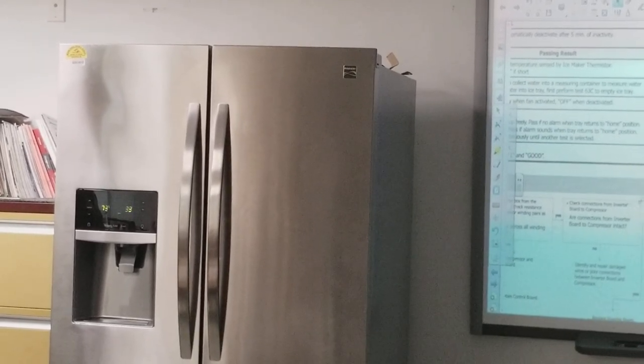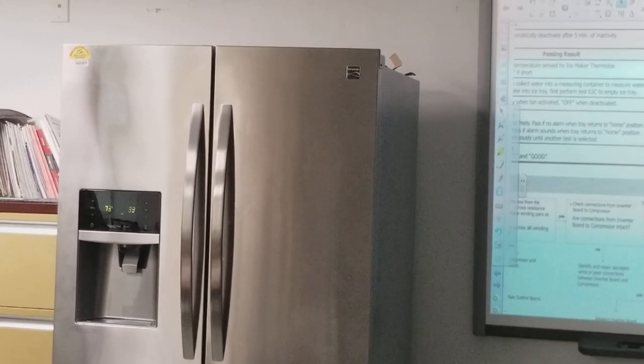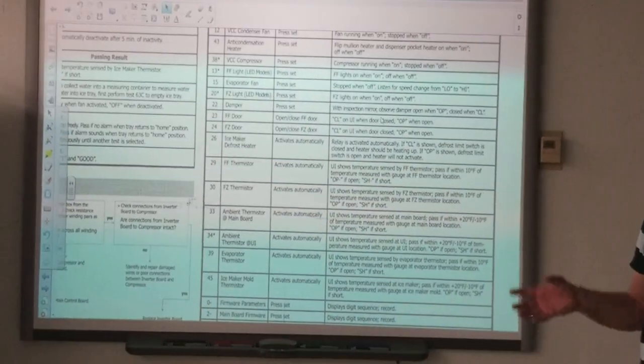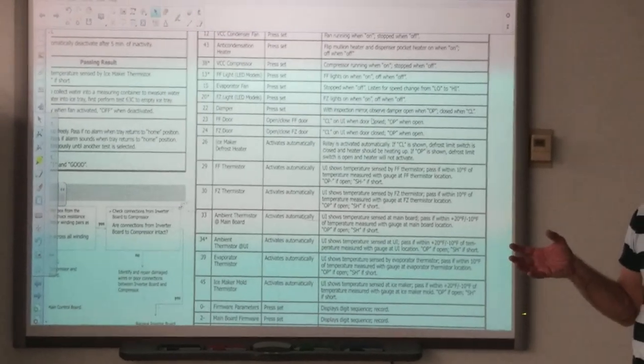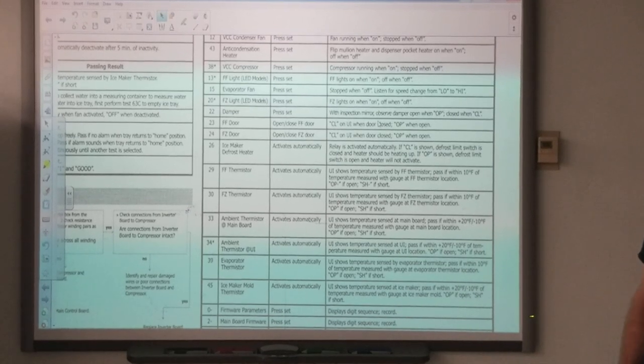But I've never had any service calls where someone had to service it because the ambient thermistor failed. Most of them are on the main board. If the ambient thermistor is bad, guess what? You have to change the whole main board. That's expensive. Okay, let's go to the next test.